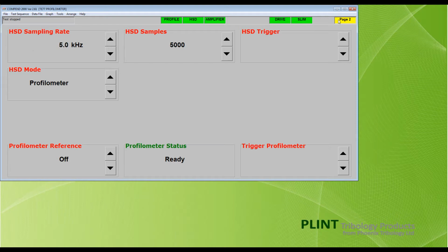The two systems, high-speed data acquisition and profilometer, are connected in parallel but used in series. High-speed data acquisition of friction, stroke and contact resistance and profilometer measurements are never used simultaneously. The HSD mode box, which is not required or shown in the standard machine configuration, is now displayed. For high-speed data acquisition, the mode is internally paced. For surface measurement, the box is set to Profilometer.